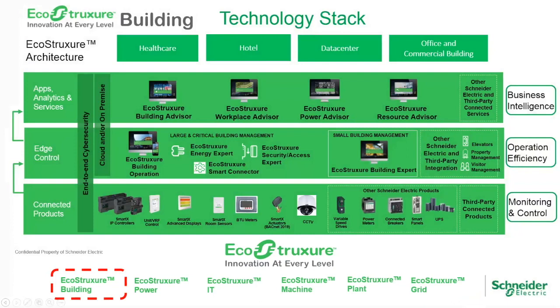This gives us an immense amount of bandwidth at the field level between all of our controllers, about 1,000 to 1,300 times more bandwidth than what we see with BACnet over MSTP. It's a huge thing happening in our industry. We're one of the leaders in doing it, but I expect you'll see everybody make this happen.